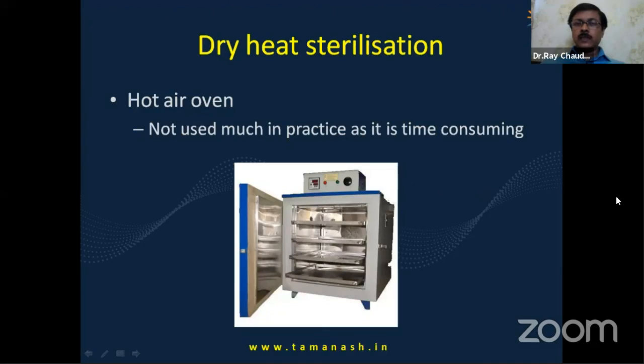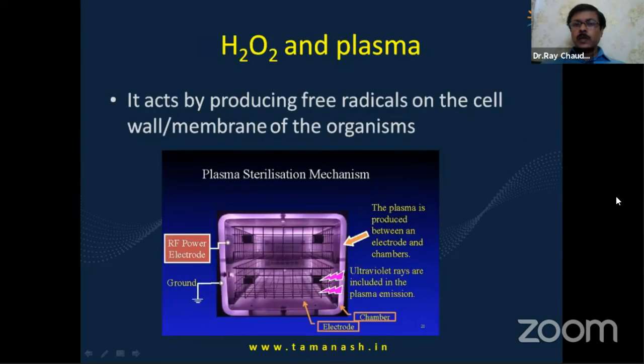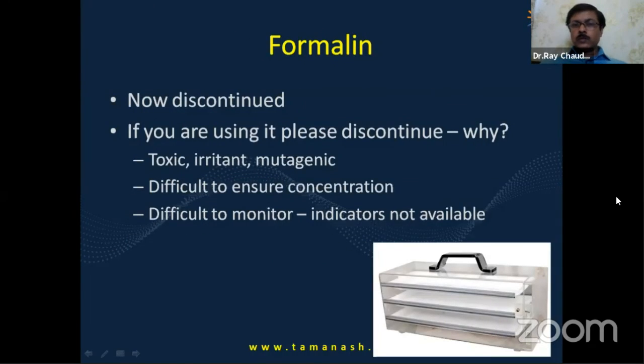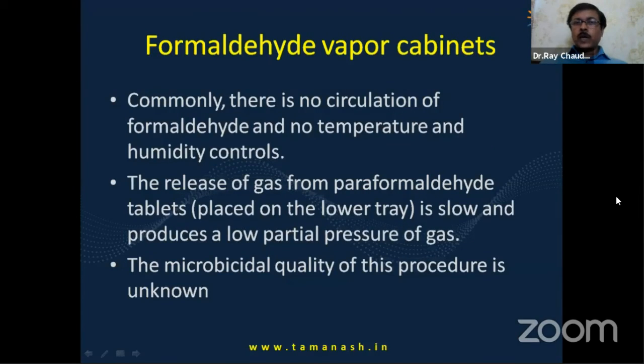Yeah, I'm concluding. Dry heat sterilization is in the form of hot air oven, which is not much in practice because it is time consuming, and H2O2 and plasma also is there, but not very commonly used. So just two more slides on formalin, because some people still use formalin. Formalin is now discontinued. If you are using it, please discontinue, because it is toxic, irritant, mutagenic, carcinogenic, and it is difficult to ensure the concentration of formalin in the chamber, and it is difficult to monitor because indicators are not available. So formaldehyde vapor cabinets or use of formalin for OT fumigation should be discontinued, because the microbicidal quality of this procedure is not known, and formaldehyde vapor is very much damaging for the staff.